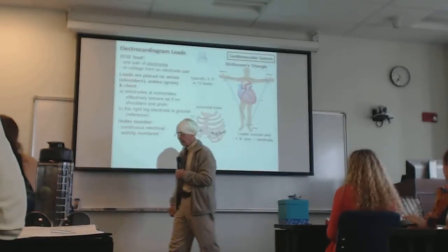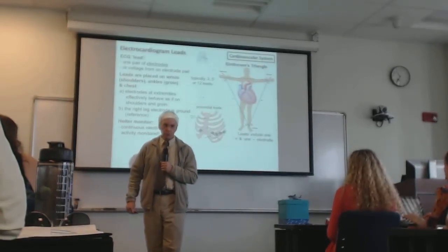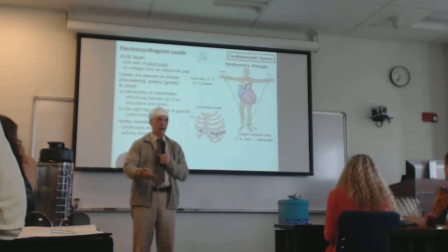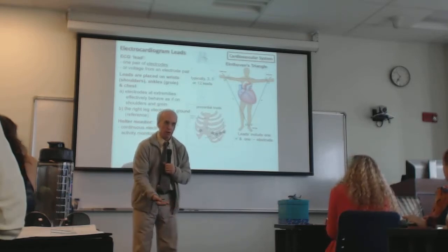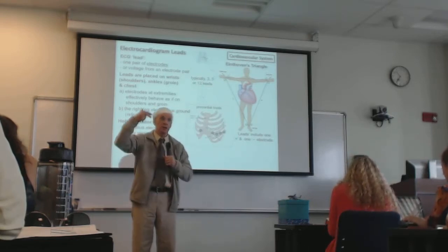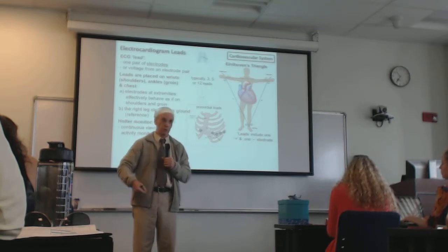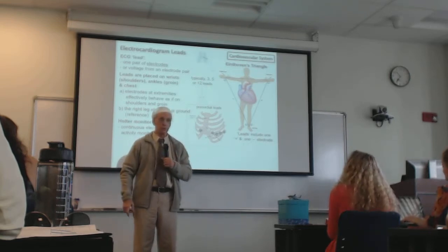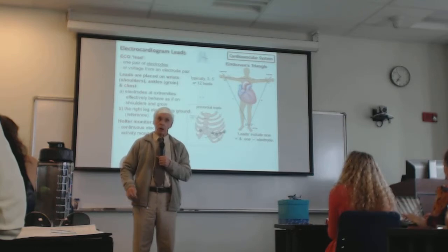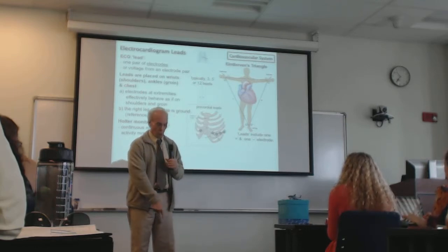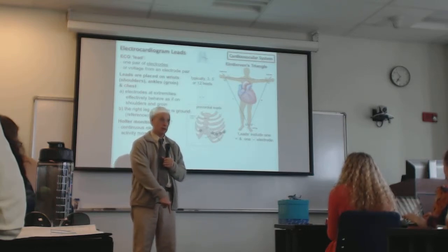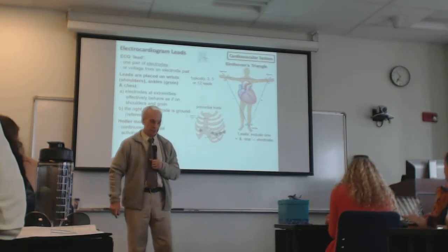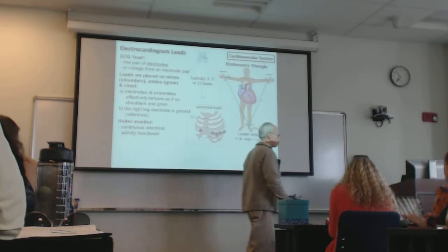So all I'm saying here is that the reference potential is analogous to establishing a standard of measure. It's a reference in all individuals. So any voltage that I measure at the arms or at the leg is going to be relative to the ground, the neutral, the sea level that is established by the other leg, usually the right leg.